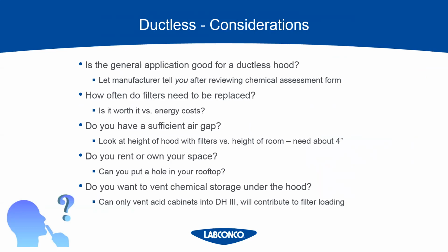If you want to vent acid or solvent cabinets through any hood, you would have to do it with a ducted hood if you wanted to vent out a solvent cabinet. And like I said, the only way to vent an acid cabinet is through a DH3. You can actually vent an acid cabinet through a fume hood, but you cannot vent a solvent cabinet into a fume hood. It has to be attached to negatively pressured ductwork above the fume hood.